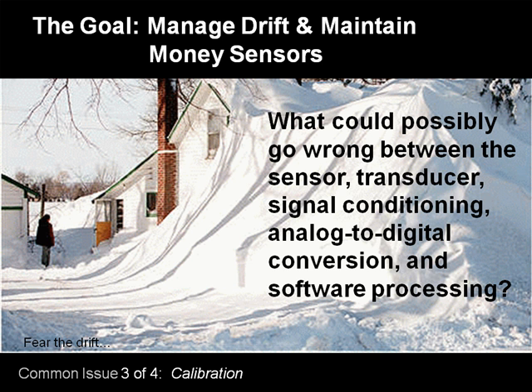The thing that I mentioned was drift, what they call in the controls community, getting out of calibration, and it can get you in as much trouble as trying to get out of it. What happened? You say, what could possibly go wrong between a calibrated control system and getting it out of calibration? Well, think about the fact that you have a sensor in a sometimes harsh environment, and it could get overheated sometimes.